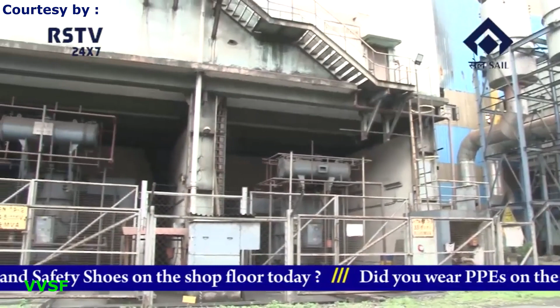Sulfuric acid dosing was conducted in the cooling water circuit of turbo blowers, and steam turbine generators were revived and commissioned to control pH of cooling water for enhancing vacuum in condensers. This facilitated reduction in consumption of steam by these equipments.